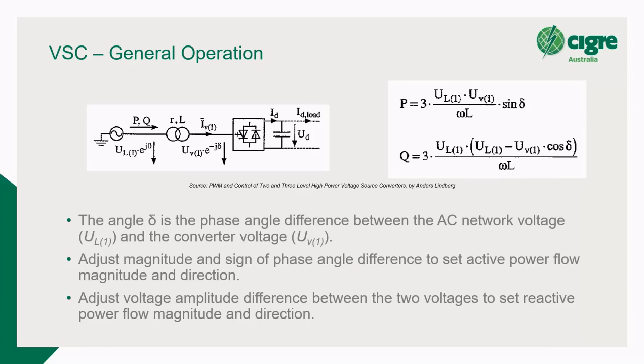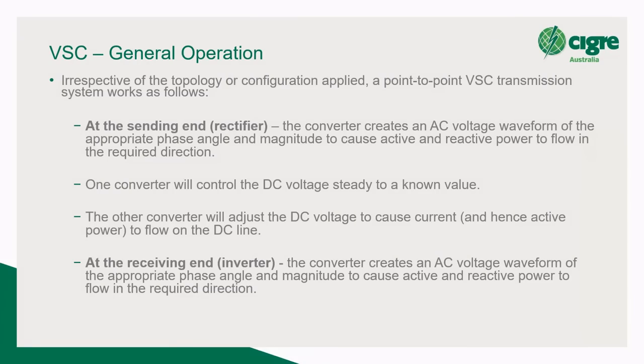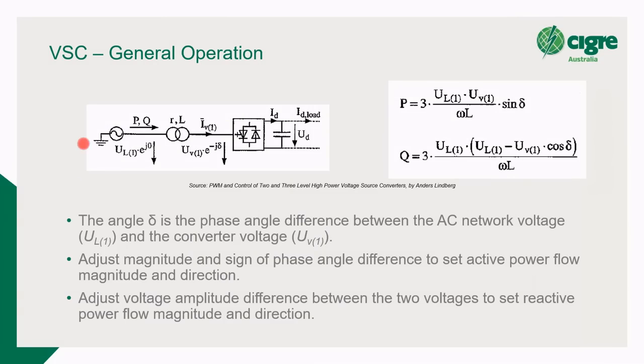Okay, next. So generally speaking, for a VSC control, there are three levels of control. One is the control at your converter, your rectifier, control across your DC line, and then control at the inverter. Effectively, with a certain degree of coordination at the sending end, the rectifier, the converter creates an AC voltage waveform of the appropriate phase angle and magnitude to allow power to flow into the converter.